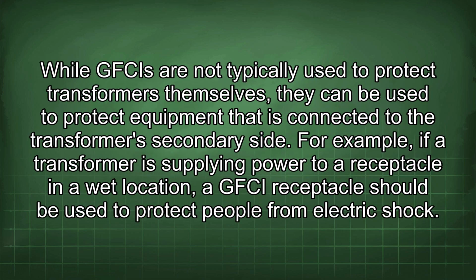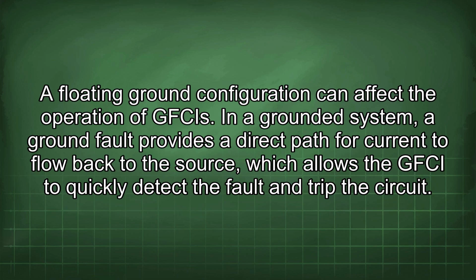While GFCIs are not typically used to protect transformers themselves, they can be used to protect equipment that is connected to the transformer's secondary side. For example, if a transformer is supplying power to a receptacle in a wet location, a GFCI receptacle should be used to protect people from electric shock. A floating ground configuration can affect the operation of GFCIs.